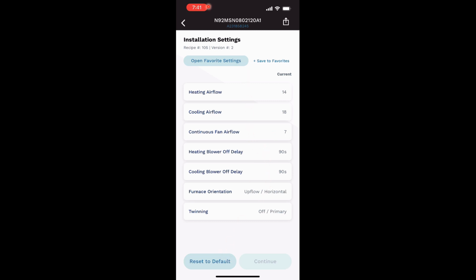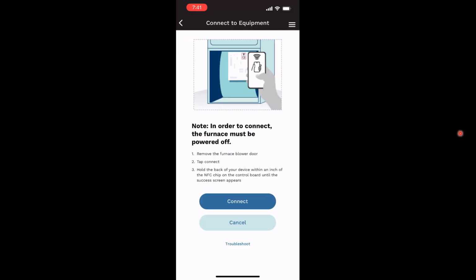And then I can save this as a favorite and call this, say, Model House A, and then the next one can be Model House B. And you do this with no power on the furnace. So when you see this app, you can't connect the app until the power's cut off. Now you have to have power to do it manually. You don't have to have power to do it with your cell phone, but you could save each setting, and then you can program every furnace for each house, and then Sharpie on the box which house it goes to, and then when they install it, it's set up properly, ready to go. So that's what's cool about this one.